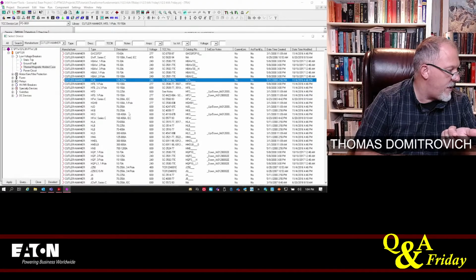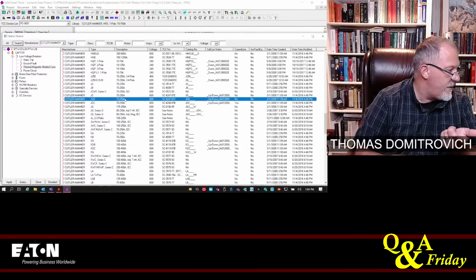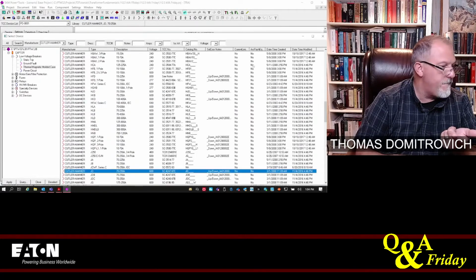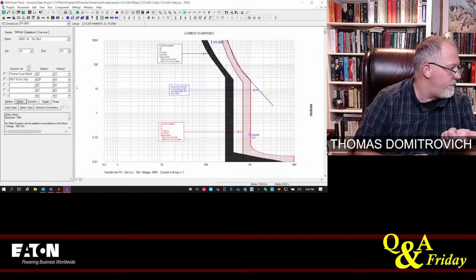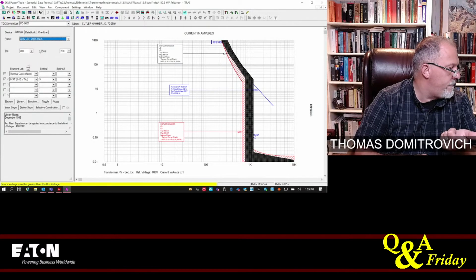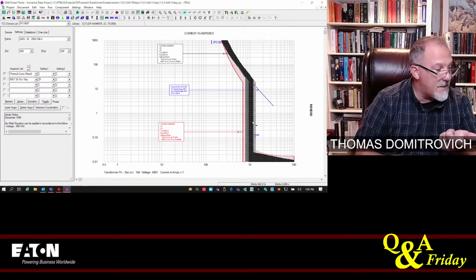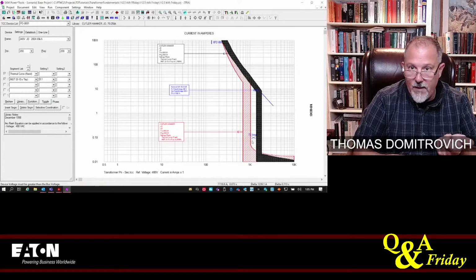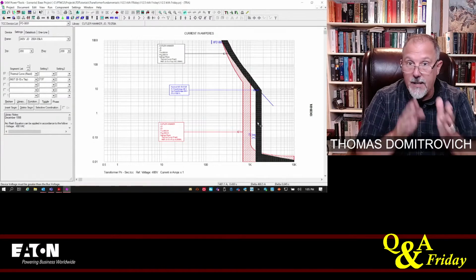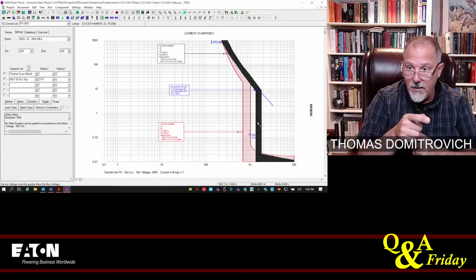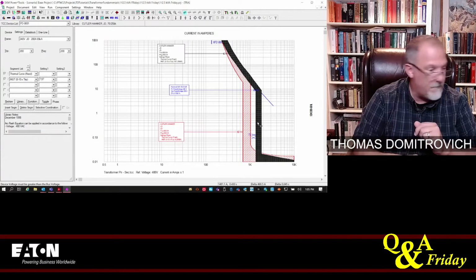225. I can do an FD. I can do a J. So we're going to do a JD breaker, and we're going to make it a 200 amp. Here we go. And I can move the instantaneous. So there it is. It works. See how I'm staying away from the inrush current? I can adjust my instantaneous. I'll have to document that so that the installer can set the dials.